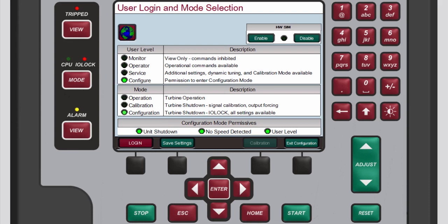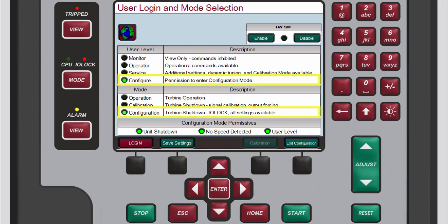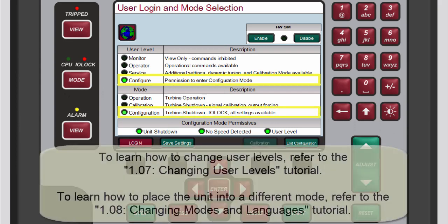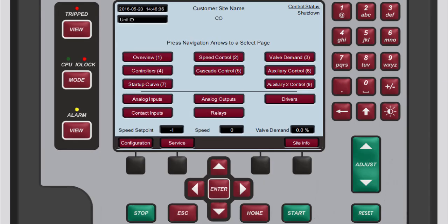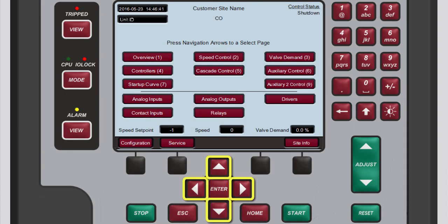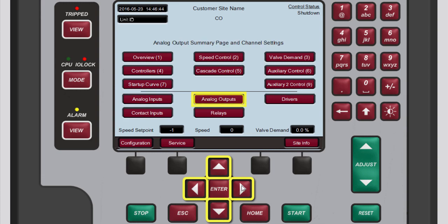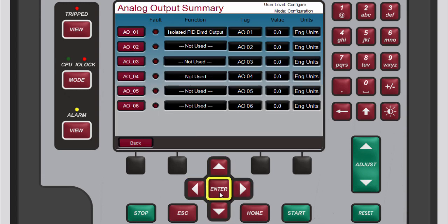To configure analog outputs you must be logged in to the configure user level and configuration mode. Refer to the changing user levels and changing modes and languages tutorials to learn how to do this. To access the analog output summary screen from the home screen, use the navigation cross keys to select analog outputs, then press enter.